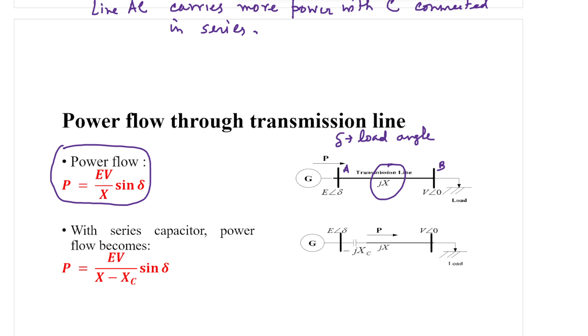Now this is the modified diagram: the same power system having generator G1 with its impedance and voltage E angle delta, and the load having voltage V angle 0. The same power is being fed from the generator to the load. Now the capacitor is being inserted. Since this capacitor is connected in series with the line, the net reactance now becomes X minus Xc.